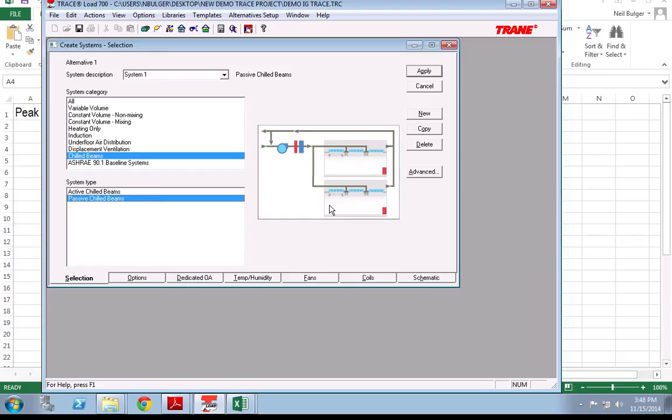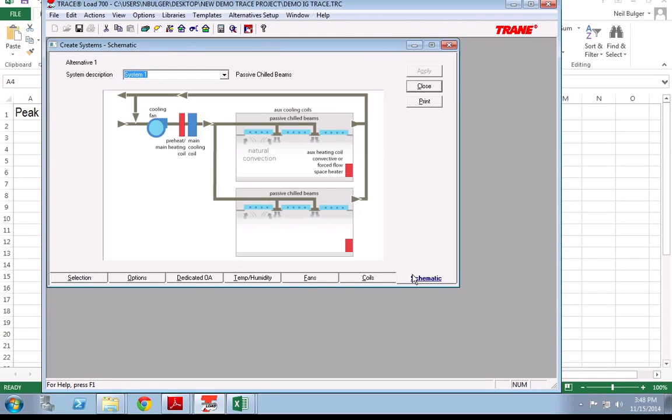We really need to know the load in each room for that room, and then we need to know the coincident peak of the building when the ventilation coil is needed, and we need to make sure that on that hour when we're trying to size the building's main air handler, each room is only using the amount of its individual radiant element as it needs to.